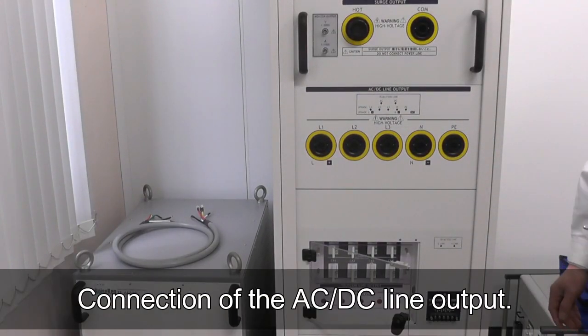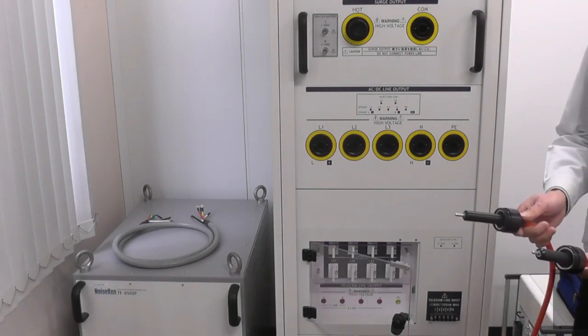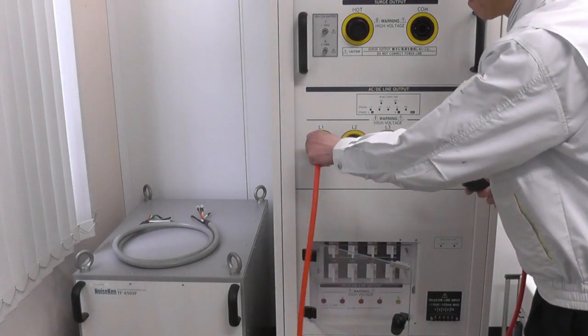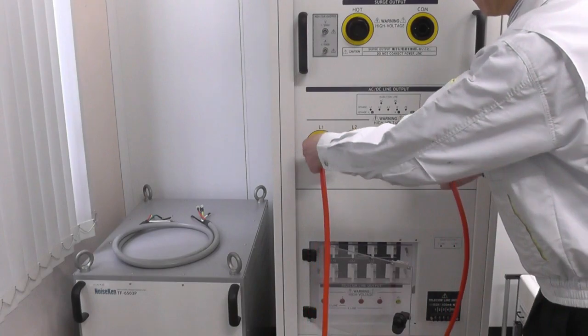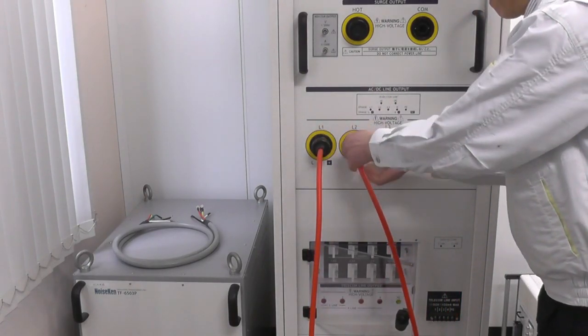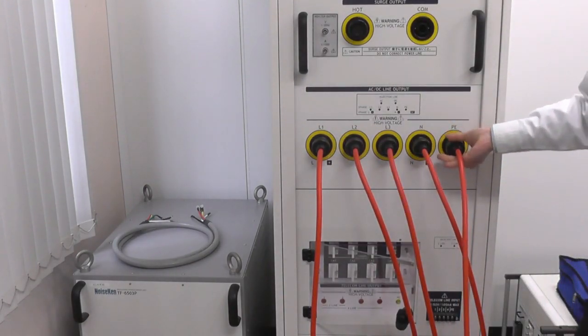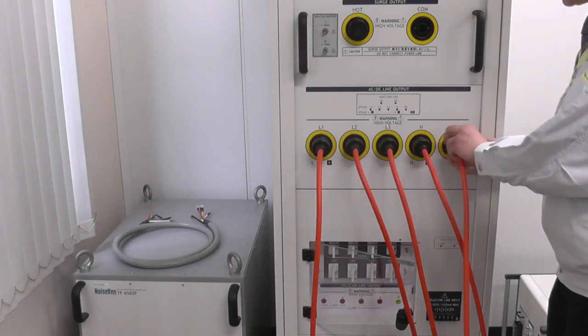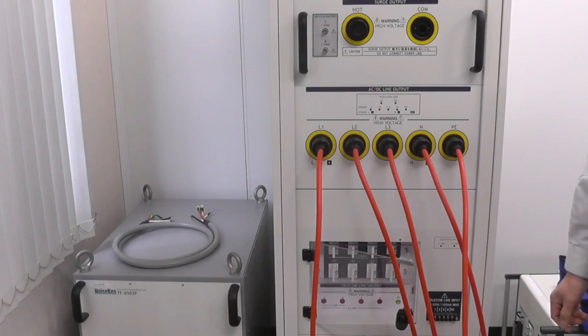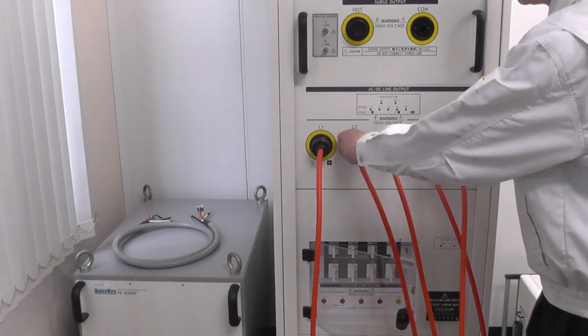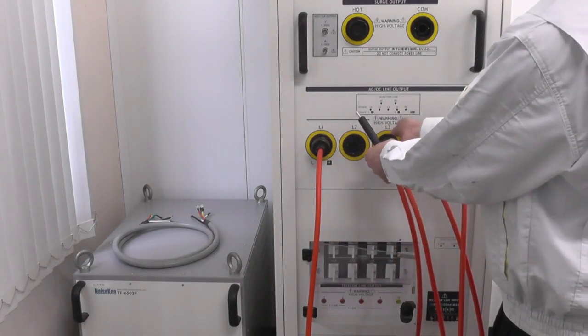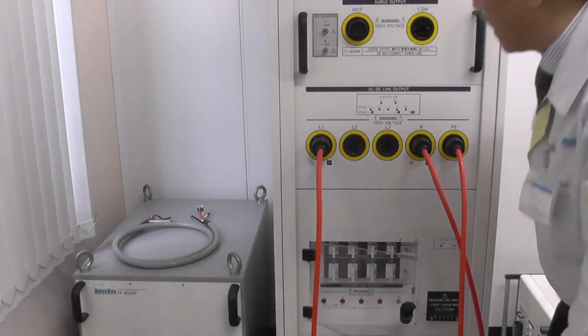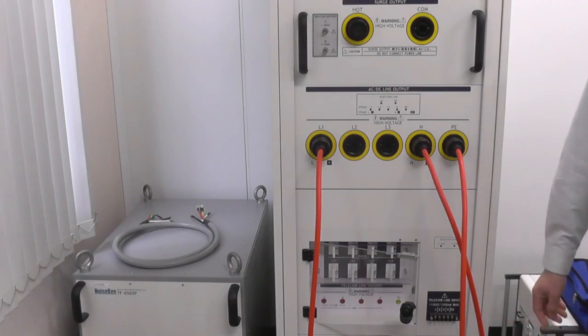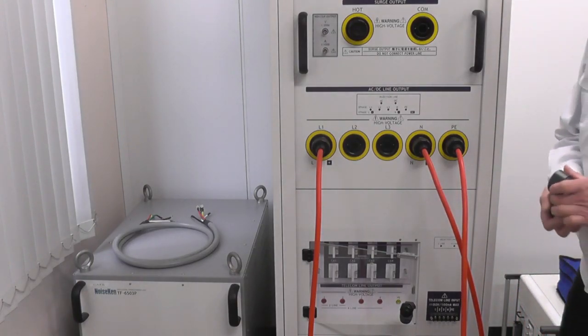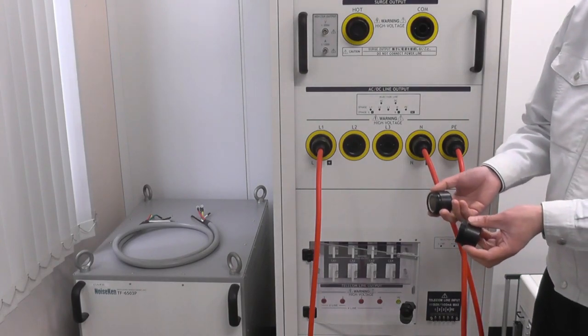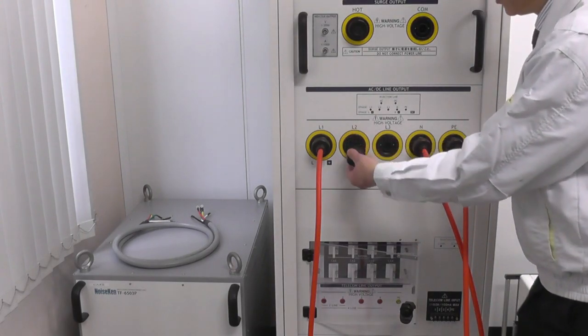For the power line output, in the case of three-phase five-line, connect the line output cables to all the line output terminals. Okay, and now all 5 lines are connected. In the case of single phase or a DC line, this is not necessary. We connect line 1, neutral line, and PE if required. And in this case, make sure to attach the connector caps to all the line output terminals which are not in use.